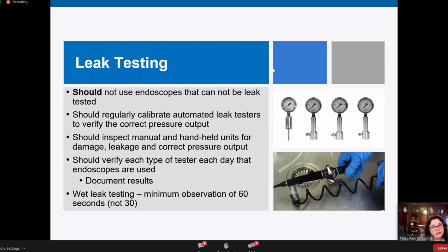But those leak testers, the pumps can wear out on them. And right now, the only quality indicator we have, it says in the IFU, is to push the pin and listen for a psht sound. But that doesn't really objectively tell you whether it's working properly or putting out the right amount of pressure, because as I said, the pumps can wear out over time. There are O-rings in the connectors. Those are considered consumable items as far as the connector, the black cord that you see in the photo there, and they should be replaced when they have signs of damage or wear and tear.